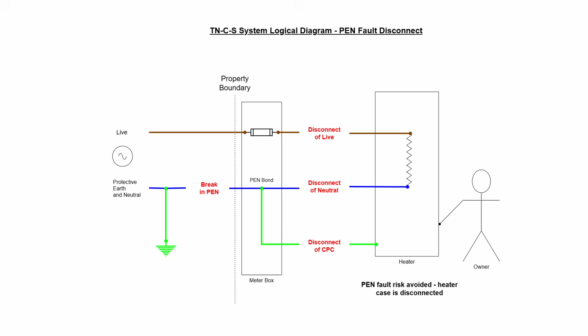The only way we can avoid this risk in the case of a PEN fault is to break the CPC. If the CPC isn't conducting, then the metalwork isn't attached to the faulty system in any way, and our person will be safe. And that's exactly how a PEN fault protector overcomes the dangerous situation. Unusually, it breaks all three conductors. It breaks the live and the neutral, and also the CPC. It's the only type of protection allowed to break the CPC.